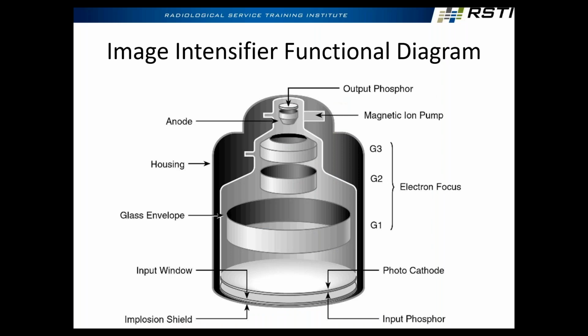This is slide 41. So entering the input phosphor, what comes in down here? Photons, x-rays come in here. This input phosphor converts photons to electrons. Electrons flow through here. We can steer them actually with these grid voltages. And then the output phosphor's job is to convert electrons to light.